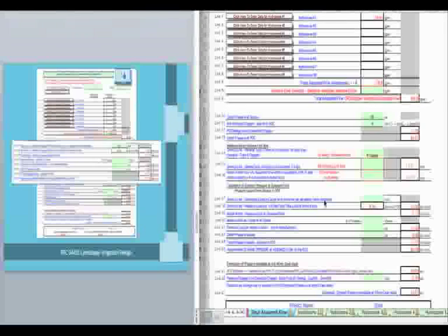So that's a piece of information that we can enter here. So service line estimated length, we're going to come up here to this cell. We're going to say 45, enter. And what it does then is it uses the information about the length of that service line, the material, type K copper, and the size to determine a PSI loss. And it does that calculation for you here. And it also determines a pressure loss through the meter based on the size of meter that was determined up here. And we didn't have any other isolation valves or other sources of pressure loss to consider, so there's nothing here.